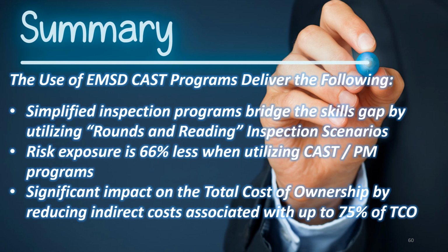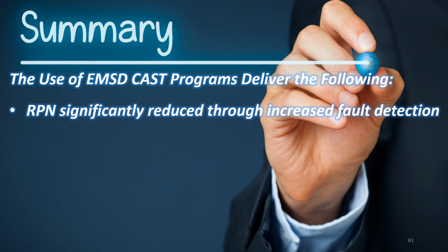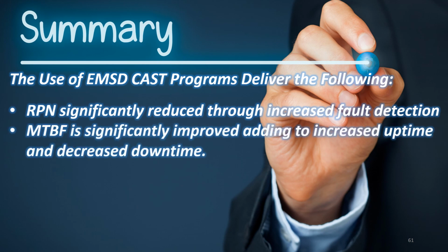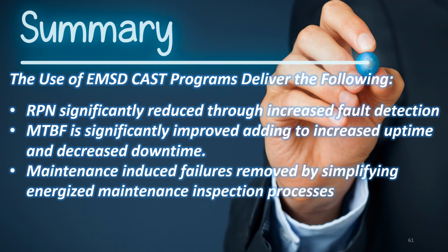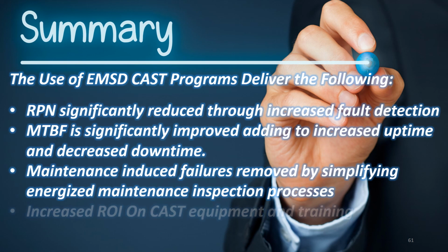I just said we reduce the indirect costs by up to 75% of TCO, so we can have a real impact on that. The risk priority number is significantly reduced by increased fault detection. Mean time between failures is significantly improved, adding to increased uptime and decreased downtime. Maintenance-induced failures are removed by simplifying energized maintenance inspection processes. If you can't get into it and you can't touch it, then the likelihood of you having an accident is relatively low. I can't really make it any lower. So we're utilizing data-driven maintenance, but the CAST and EMSD program ensures that I can get all this data without ever putting anyone in harm's way.